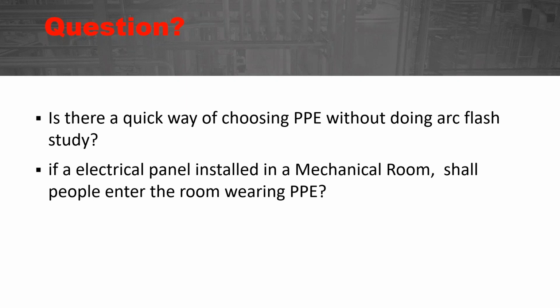Well, category 0 was taken out, it was eliminated, but what came in its place was the term normal operating conditions, which Jay mentioned some of these. And as long as the equipment is in normal operating condition, no PPE is needed. So going into this room, as long as everything in the room is in normal operating condition, then wearing PPE into that room is not required.